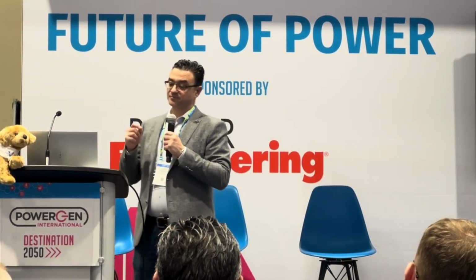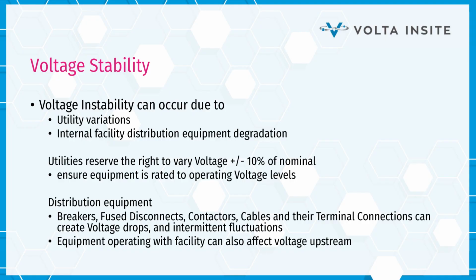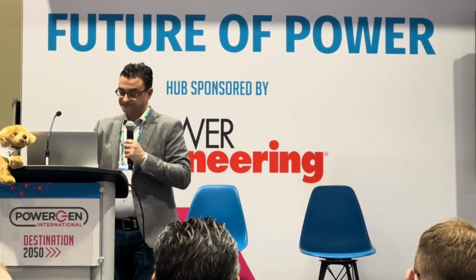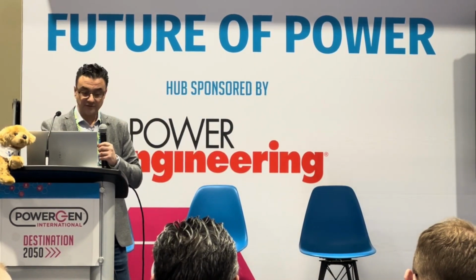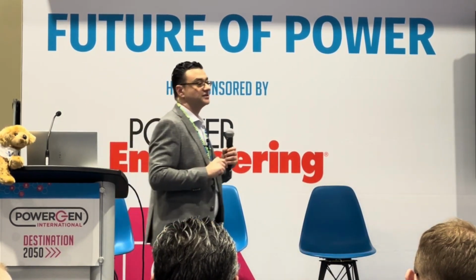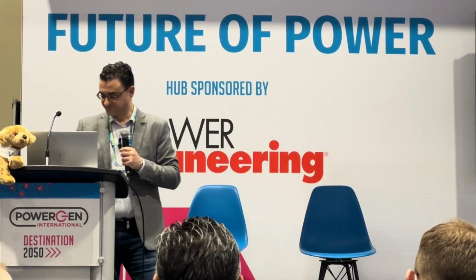Additionally, within a particular facility, now you have a distribution system. You have breakers, fuse disconnects, contactors, terminal connections. If any of those things are degrading, i.e. you have loose connections, or you have contactors that have built up a lot of carbon buildup because of arcing, you can get voltage drops and you can get intermittent fluctuations. You can lose power. And of course, if you also have equipment, like a lot of VFDs within a facility, you can create a lot of harmonic distortion.